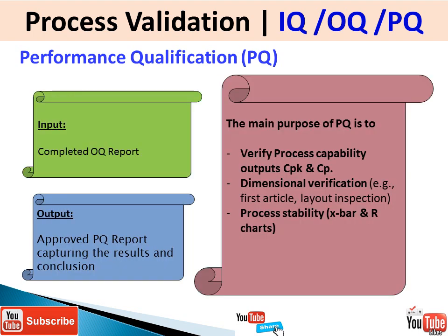For PQ, the input is the completed OQ report, and the output is an approved PQ report capturing the results and conclusions. During PQ, we verify process capability outputs such as Cpk and Cp, perform dimensional verification like first article inspection and layout inspection, and conduct process stability studies using X-bar and R charts.